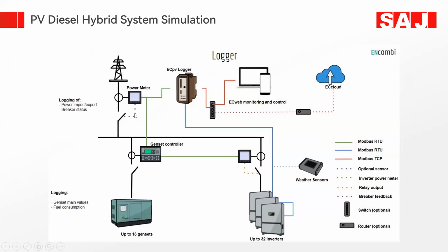You have a power meter on your grid side, and it shows the data on the ECPV logger of EN Combi. Then it will upload to the monitoring module. The ECPV logger is also connected with the inverters and gensets. Genset controllers control the inverter production and curtail the power if you don't need to export the power to the grid.